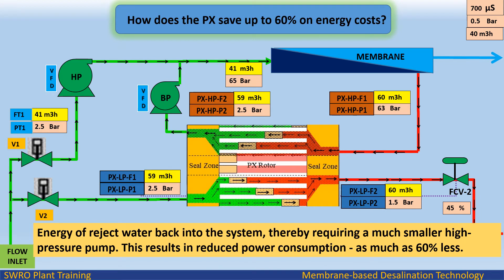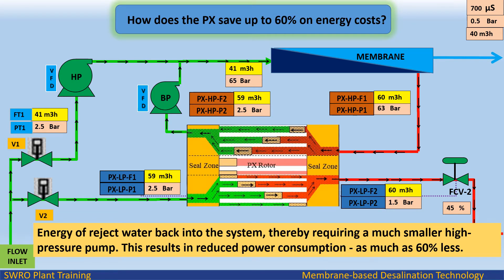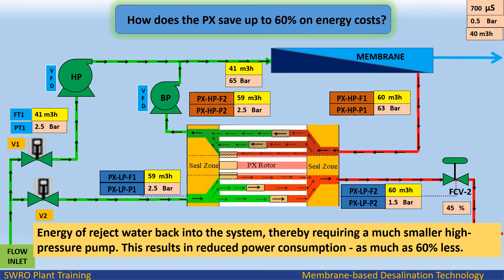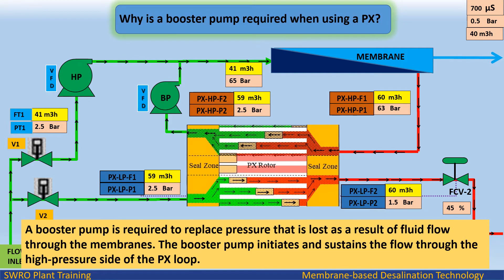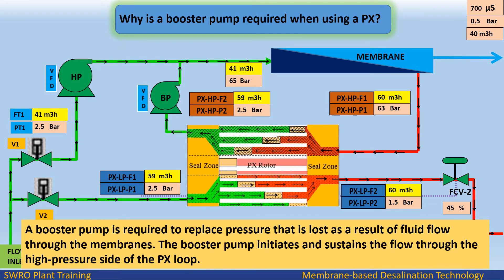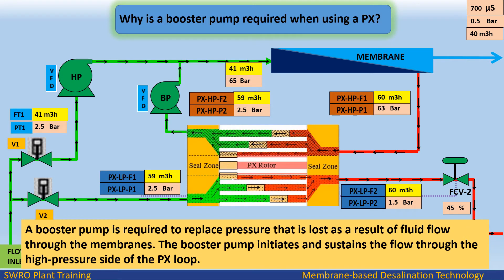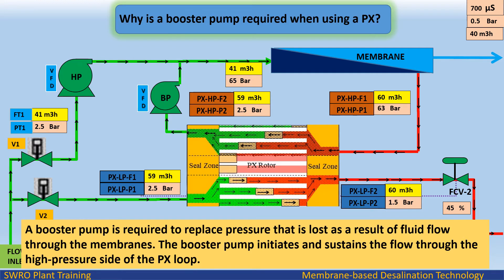The PX saves up to 60% on energy costs by recycling the energy of reject water back into the system, thereby requiring a much smaller high-pressure pump. This results in reduced power consumption — as much as 60% less. A booster pump is required when using a PX ERD to replace pressure lost due to fluid flow through the membranes. The booster pump initiates and sustains flow through the high-pressure side of the PX loop.